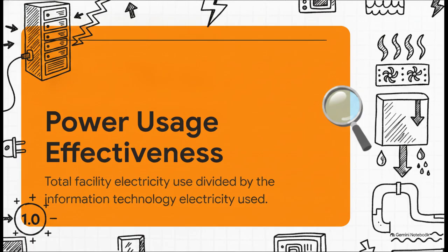Power usage effectiveness, or PUE, is basically the gold standard for data center efficiency. It's the total electricity use of a facility divided by the IT electricity used. So an ideal PUE is 1.0, meaning every single watt entering the building goes strictly into productive computing, with zero waste on overhead like cooling or lights.